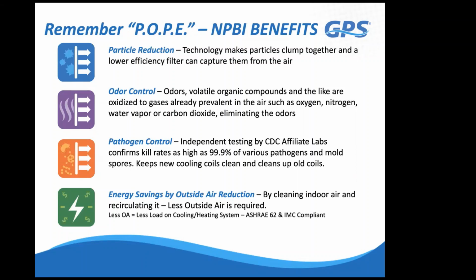With pathogen control, we're treating the pathogens in the air handlers where the devices are mounted, but we're also treating them downstream. Now, one thing I don't believe I covered in this presentation is if you do have a final filter in your systems, like in a healthcare application, you have to put these devices after the final filter in order for the ions to treat the space, because the final filter or any filter that's MERV 8 or greater are easily going to stop these ions. And so if you want to treat your space, a lot of hospitals are putting in 2 sets of bars, one on the coils and one after the HEPA filters in order to treat downstream into that space.